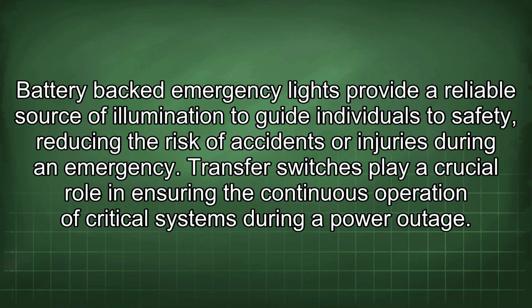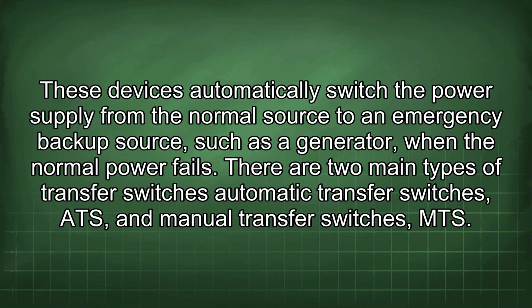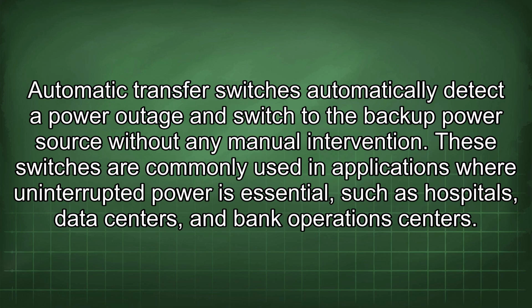Battery-backed emergency lights provide a reliable source of illumination to guide individuals to safety, reducing the risk of accidents or injuries during an emergency. Transfer switches play a crucial role in ensuring the continuous operation of critical systems during a power outage. These devices automatically switch the power supply from the normal source to an emergency backup source, such as a generator, when the normal power fails. There are two main types of transfer switches: automatic transfer switches (ATS) and manual transfer switches (MTS). Automatic transfer switches automatically detect a power outage and switch to the backup power source without any manual intervention.